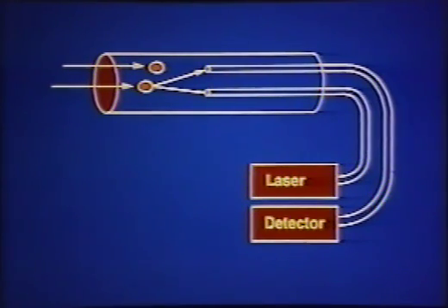The laser Doppler catheter consists of fiber optic light guides that are fashioned together into the form of a thin catheter, and with a system such as this, we use a fiber to deliver laser light to the flowing blood, another fiber to collect the scattered light and carry it back to an appropriate detector.